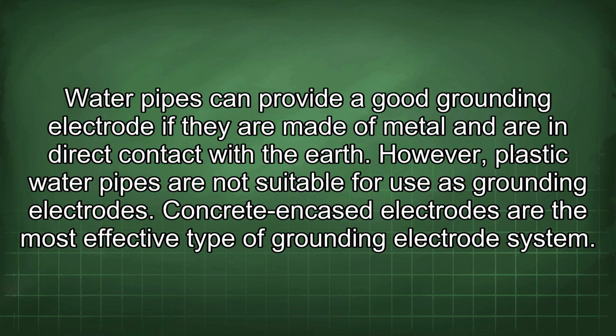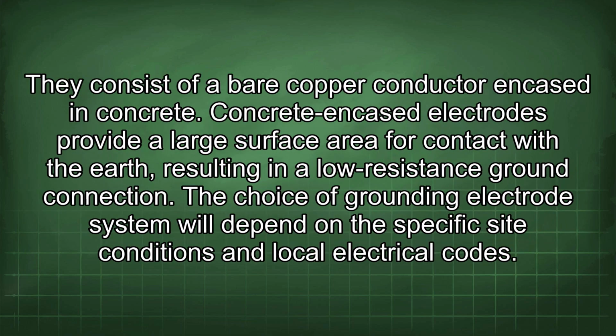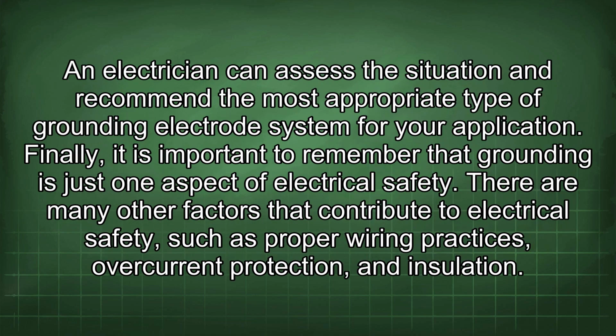Water pipes can provide a good grounding electrode if they are made of metal and are in direct contact with the earth. However, plastic water pipes are not suitable for use as grounding electrodes. Concrete-encased electrodes are the most effective type of grounding electrode system. They consist of a bare copper conductor encased in concrete. Concrete-encased electrodes provide a large surface area for contact with the earth, resulting in a low-resistance ground connection. The choice of grounding electrode system will depend on the specific site conditions and local electrical codes. An electrician can assess the situation and recommend the most appropriate type of grounding electrode system for your application.